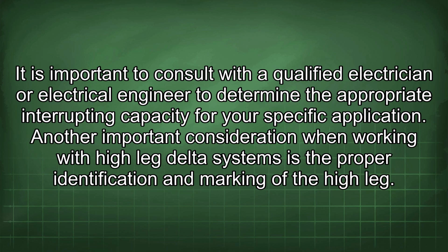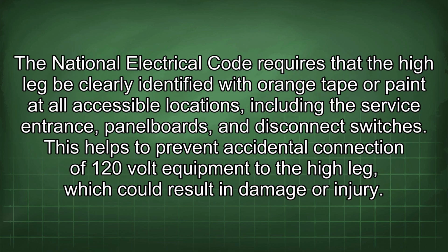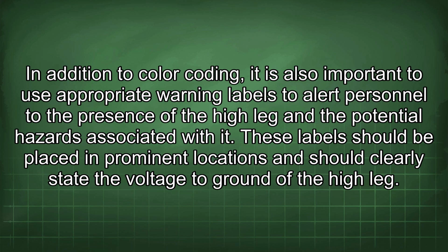specific application. Another important consideration when working with high-leg delta systems is the proper identification and marking of the high leg. The National Electrical Code requires that the high leg be clearly identified with orange tape or paint at all accessible locations, including the service entrance, panel boards, and disconnect switches. This helps to prevent accidental connection of 120-volt equipment to the high leg, which could result in damage or injury. In addition to color coding, it is also important to use appropriate warning labels to alert personnel to the presence of the high leg and the potential hazards associated with it. These labels should be placed in prominent locations and should clearly state the voltage to ground of the high leg.